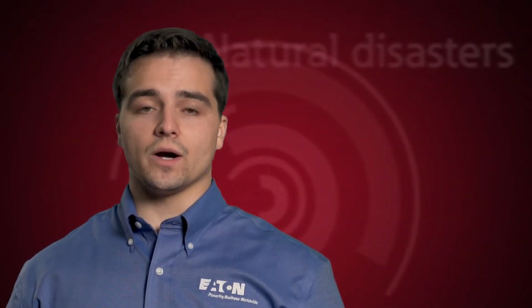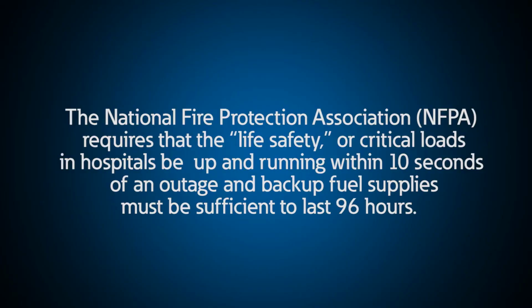Healthcare facilities, especially hospitals, are also critical and must be supported during disruptive events. For example, the National Fire Protection Association requires that life safety or critical loads in hospitals be up and running within 10 seconds of an outage, and backup fuel supplies must be sufficient to last 96 hours.